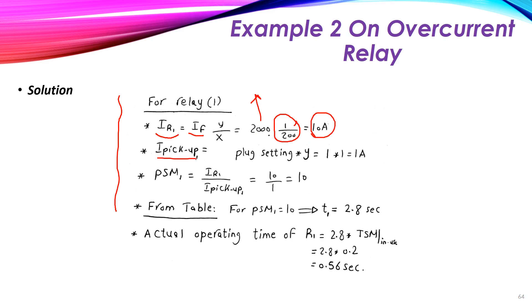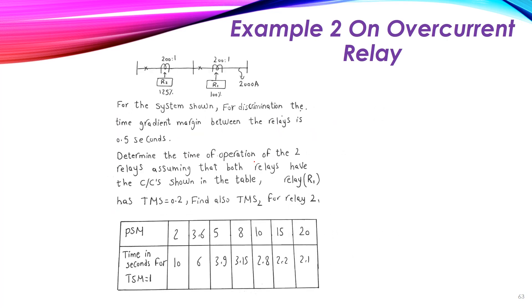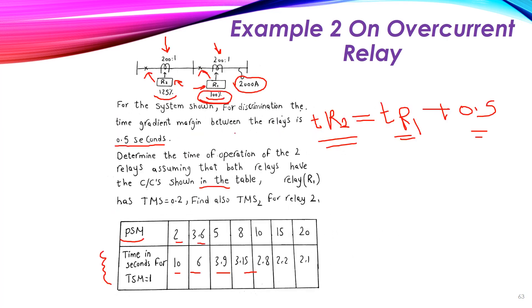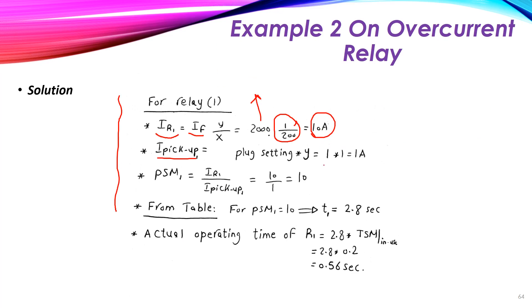The pickup current flowing inside the relay will be equal to the plug setting multiplied by the CT secondary. The plug setting is 100% and the secondary is 1 ampere, so it will be 1 times 1 ampere, giving us 1 ampere. The plug setting multiplier is equal to the actual current value of 10 amperes over the pickup current of 1 ampere.